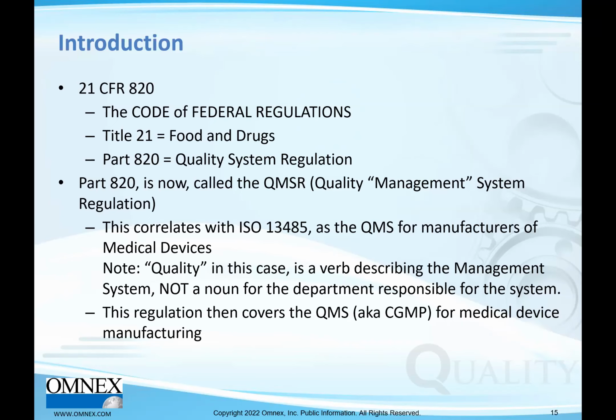Note, quality in this case is a verb describing the management system, not a noun for the department responsible for the system. So if anything, the emphasis is being taken off of quality system regulation and it's more focused on management of that system. So keep that in mind, take that back to your various companies and make sure it's stressed that it's a management system, not a quality department system. This regulation then covers the QMS, otherwise known as CGMP, current good manufacturing practice for medical device manufacturing.